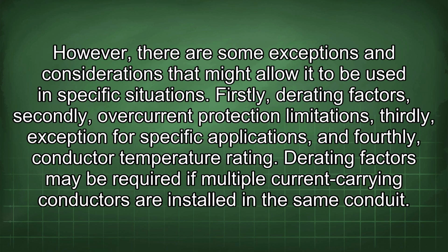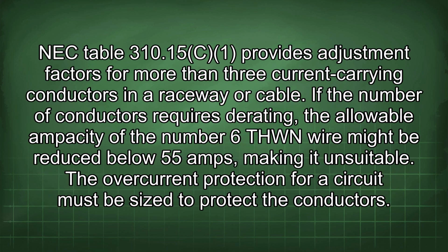However, there are some exceptions and considerations that might allow it to be used in specific situations. Firstly, derating factors. Secondly, overcurrent protection limitations. Thirdly, exception for specific applications. And fourthly, conductor temperature rating. Derating factors may be required if multiple current carrying conductors are installed in the same conduit. NEC Table 310.15(C)(1) provides adjustment factors for more than 3 current carrying conductors in a raceway or cable. If the number of conductors requires derating, the allowable ampacity of the number 6 THWN wire might be reduced below 55 amps, making it unsuitable.